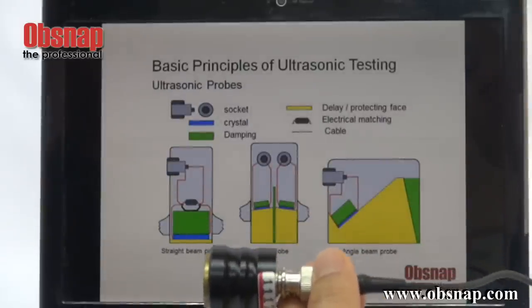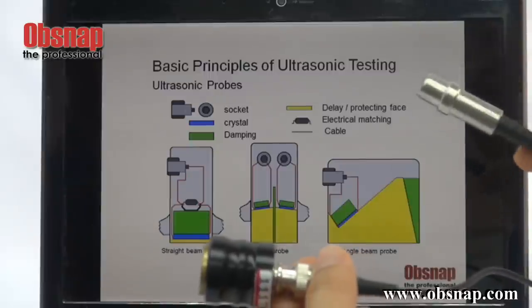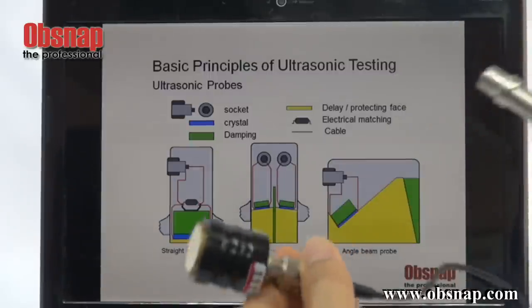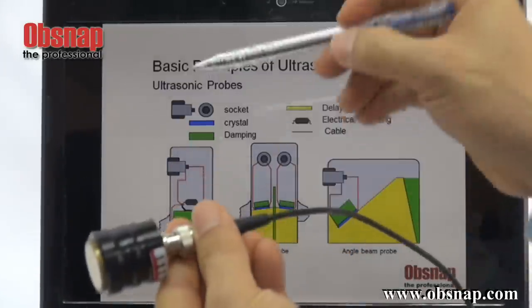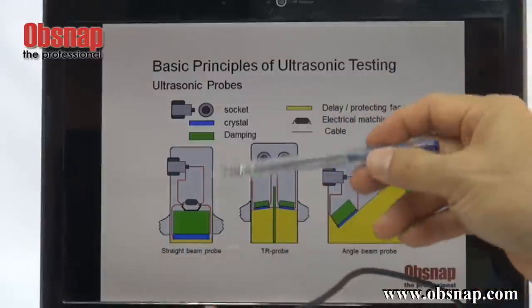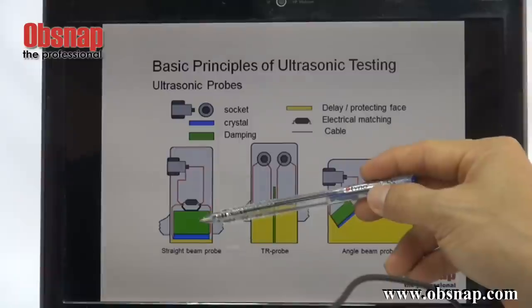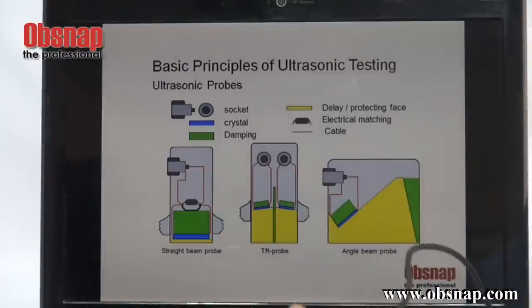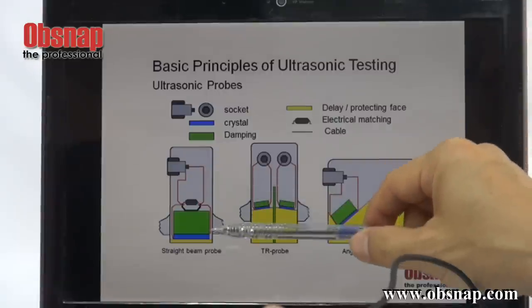Here are the three main sensors we use for ultrasonic testing purposes. This is called the straight beam probe. This is the crystal, this is the damping material, and its purpose is actually to improve the amplitude, the width, and the resolution of the echo for display purposes.